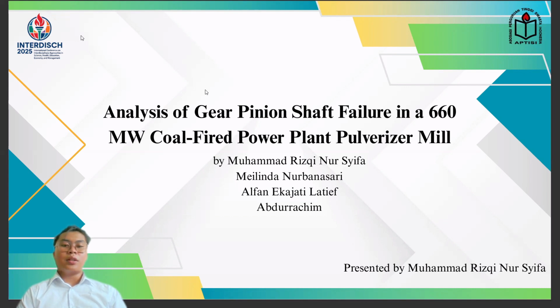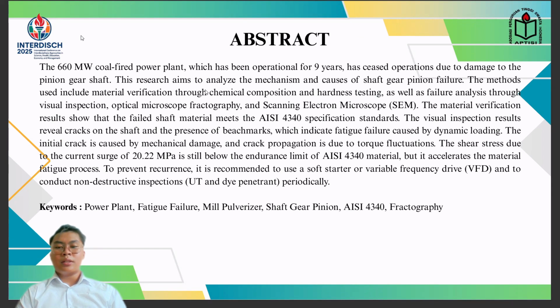I will present my article titled Analysis of Gear Pinion Shaft Failure in a 660 megawatt coal-fired power plant for Pulverizer Mill. First, this slide shows the abstract, which indicates the operational status of the shaft over 9 years. The shaft has experienced damage, and material verification and failure analysis will be conducted to determine the failure mechanism and provide recommendations to prevent a similar incident from happening again.